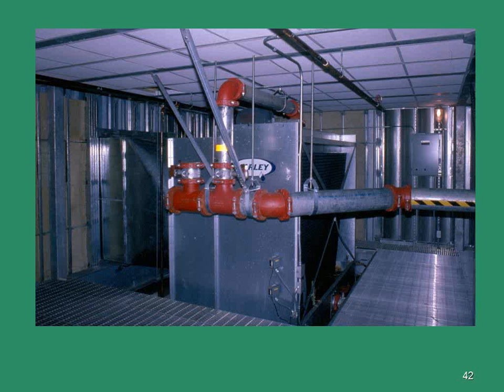What if you had a situation like an air-cooled chiller outdoors right next to a condominium or student housing? It's going to be disruptive. Even if it's not against jurisdictional law, if there are complaints, what can the owner do to take care of it? There are various things. Sometimes we build an enclosure around a couple of sides, from the chiller to the facade of the building. Sometimes we use a silencer package. Sometimes we just put it in a remote location. That's why it's good to ask the question early, because once you turn the thing on and realize you have a noise problem, it's expensive to fix.